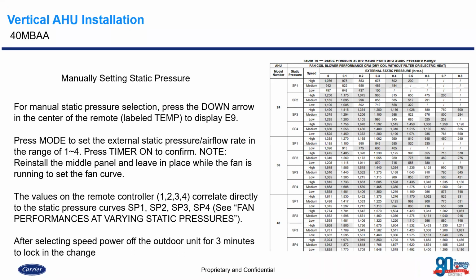Okay. Now, if we look to the right, you'll see this chart that has the model number and tonnage of the equipment with different static pressure settings. So we see our 2, 3, and 4-ton models, and of course we want to find our applicable model. Say, for example, we have a 2-ton model. When we're at that E9 code on that wireless controller, we want to hit the mode button, and you're going to see a 1, 2, 3, and 4, which is essentially SP1, SP2, SP3, and SP4.